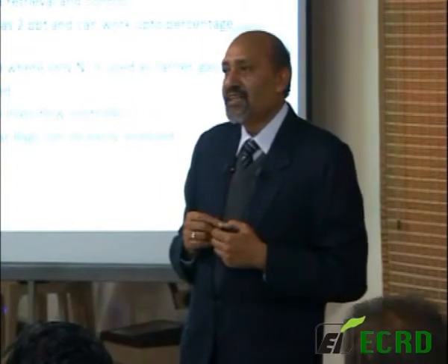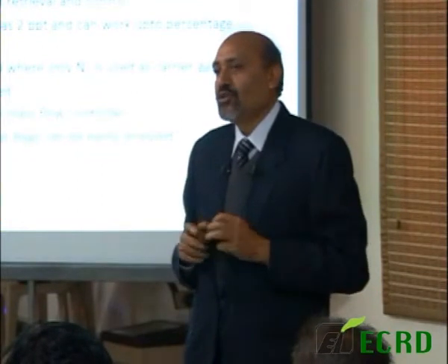So I find that with a standard size nitrogen cylinder, their system flows are so low that I think the cylinder lasts 3 months or so. High purity, 5-9 purity nitrogen you have to provide, but it's available now in the country.